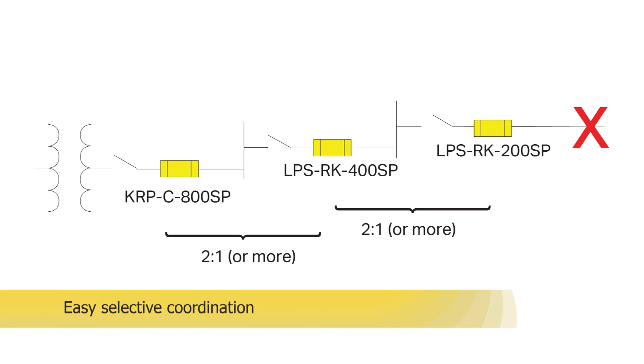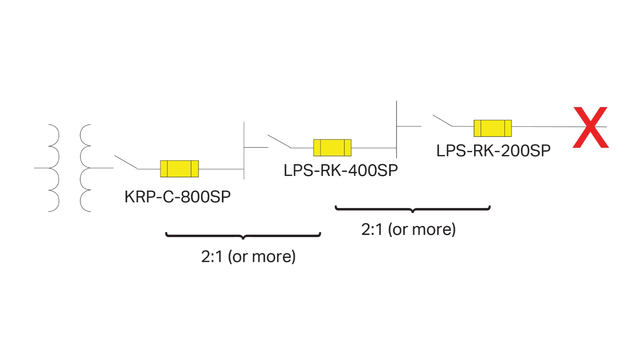Current limitation is a key part of selective coordination, and current limiting fuses save the engineer or designer time and money by reducing the need for a selective coordination study, as long as the minimum amp ratio is maintained between upstream and downstream fuses, such as a 2:1 amp rating ratio for Bussmann series Low-Peak fuses. Selective coordination is achieved and unnecessary power loss to upstream circuits is prevented for any fault current up to the interrupting rating of the fuse.